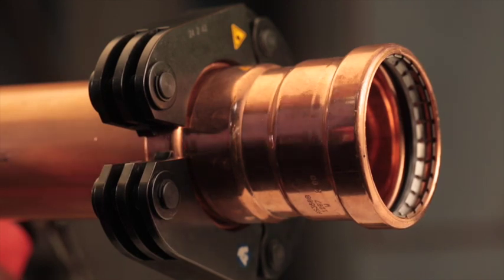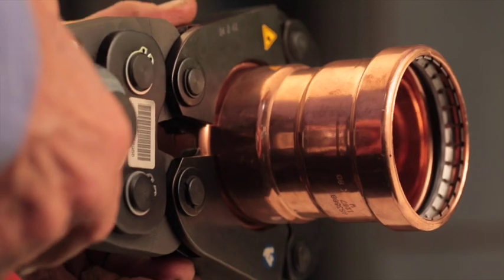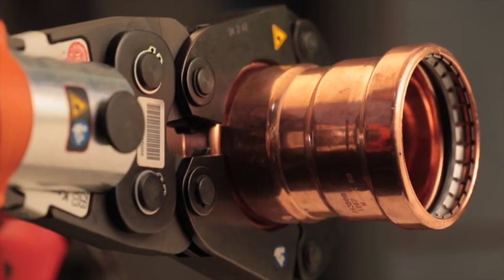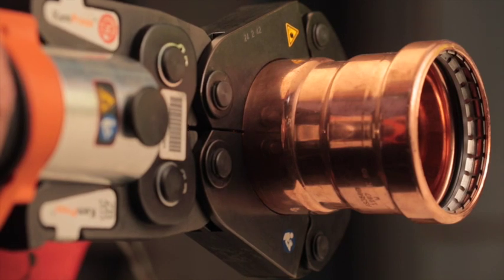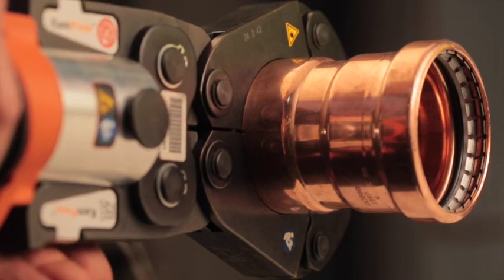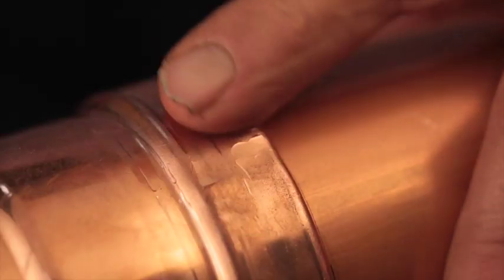Depress the jaw levers and attach to the press collar so that the claws of the jaw grip around the pins of the press collar. Ensure the fitting still lines up with the insertion depth on the tube. Press the start button to make the press. Release the adapter jaw from the collar and the collar from the fitting. Visually inspect the fitting and remove the Kempress label to indicate completion of the press.